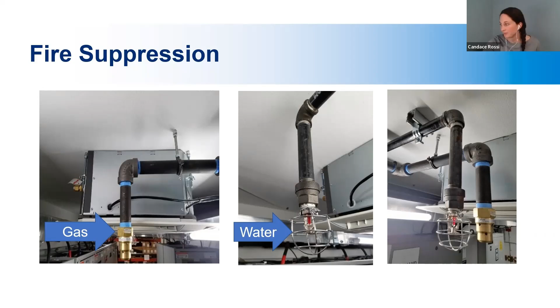Also within explosion control are fire suppression systems. This is the same system in Brooklyn I just talked about. They have a gas system set up throughout the unit along with water, working in tandem. Their clean agent comes out of the gas system, but they also have water, because at the end of the day, the only way to really put out a battery fire that's past the point of no return is by soaking it in water. With these containers, if the doors have not been opened, water from a dry pipe system will come in and completely fill the storage container to dissipate the fire.